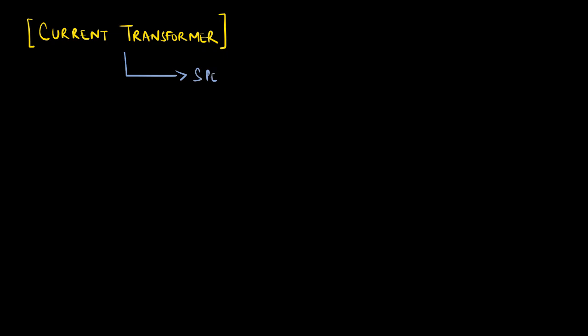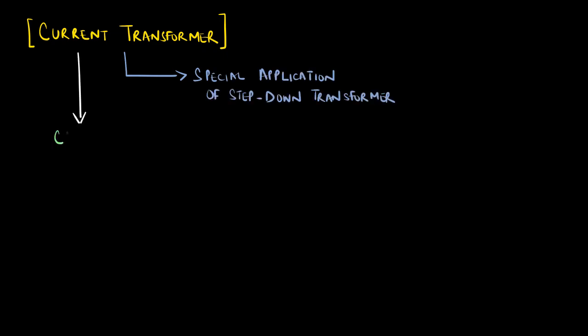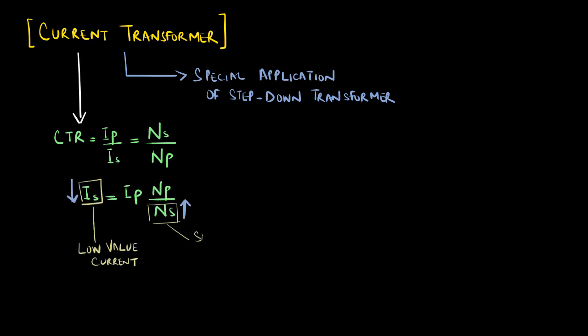Current transformers are a very special application of a step down transformer. In order to have a smaller amount of current on the secondary side of the CT, the number of turns on the secondary side must be greater than the number of turns on the primary side.